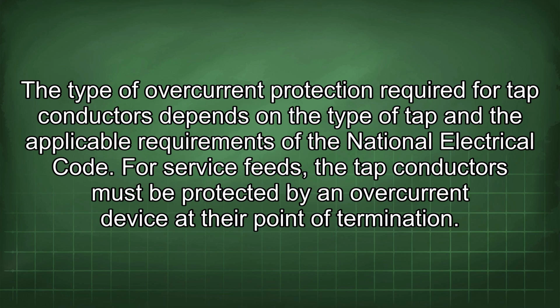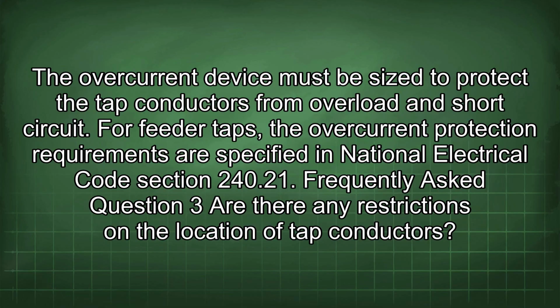For service feeds, the tap conductors must be protected by an overcurrent device at their point of termination. The overcurrent device must be sized to protect the tap conductors from overload and short circuit. For feeder taps, the overcurrent protection requirements are specified in National Electrical Code Section 240.21.